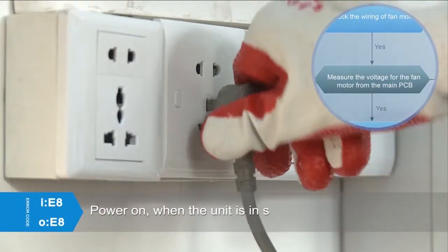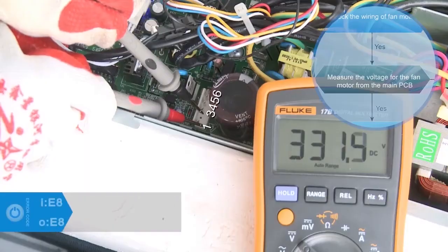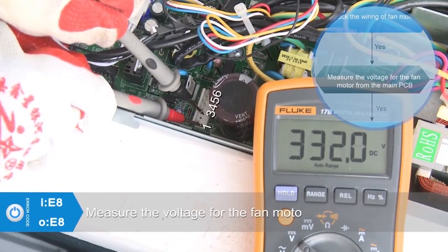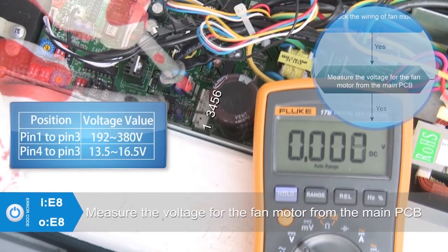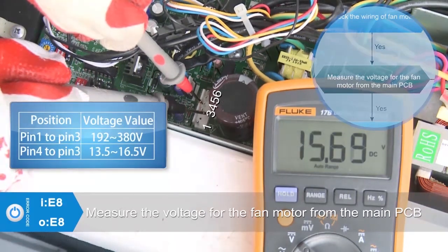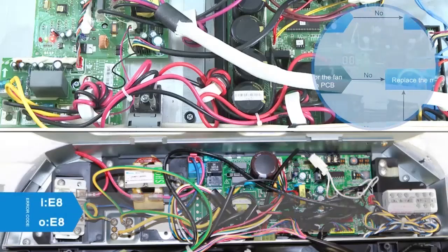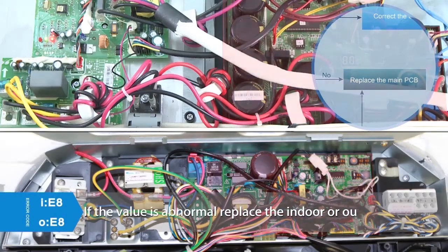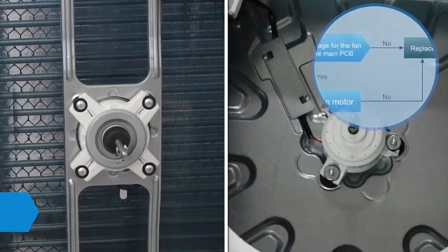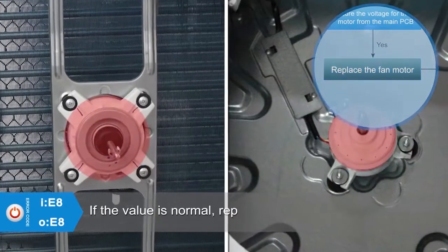Power on. When the unit is in standby mode, measure the voltage of pin 1 to pin 3, and pin 4 to pin 3 in the fan motor connectors. If the value of the voltage is not in the range shown in the table, replace the PCB. If the value is normal, replace the fan motor.